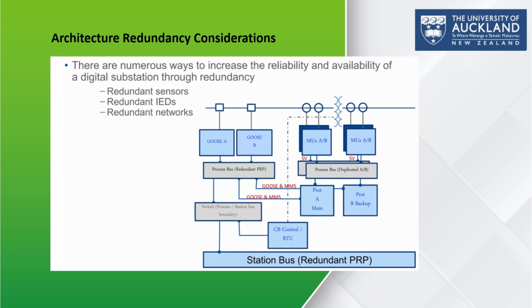Next, the substation includes redundant intelligent electronic devices, shown as protection A main and protection B backup relays. If one IED fails, the second takes over without interrupting protection functions. The communication network itself is also fully redundant. The system uses parallel redundancy protocol, that is PRP, on both the process bus and station bus, ensuring that every message is sent simultaneously on two independent networks. This guarantees zero-time recovery if a communication link fails.